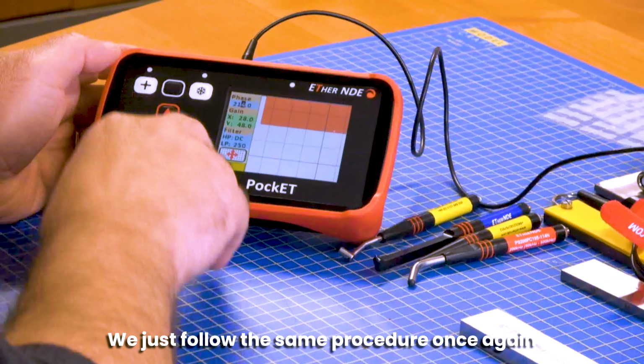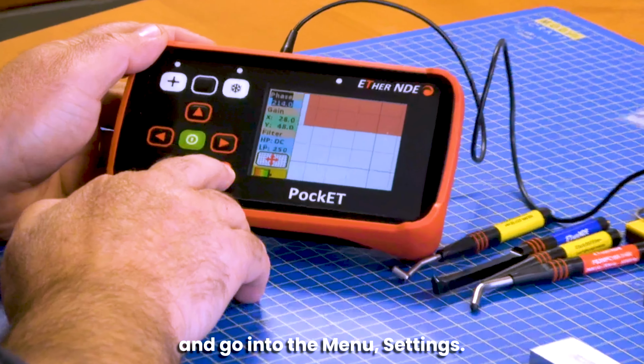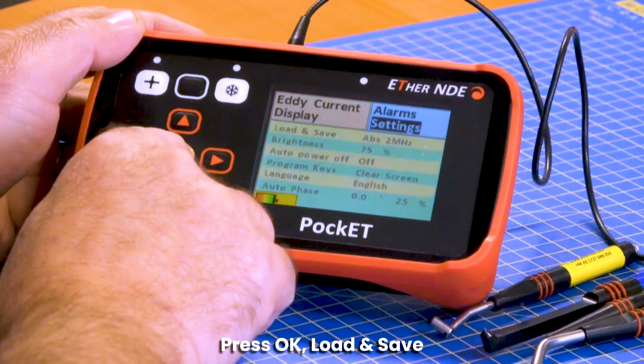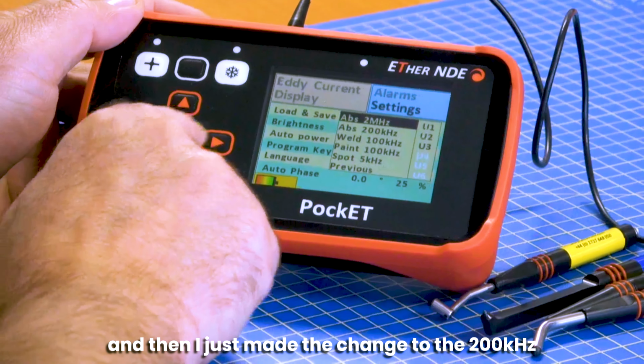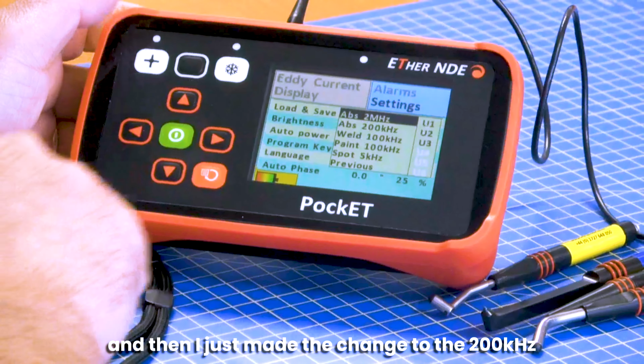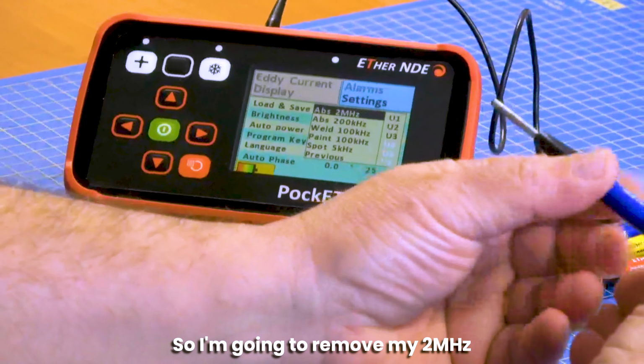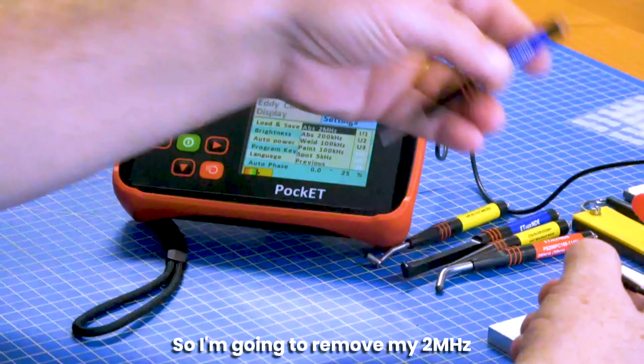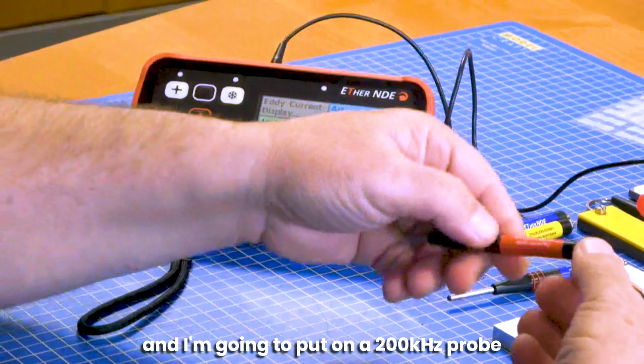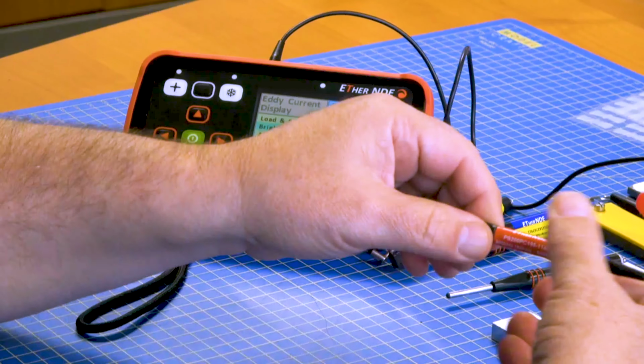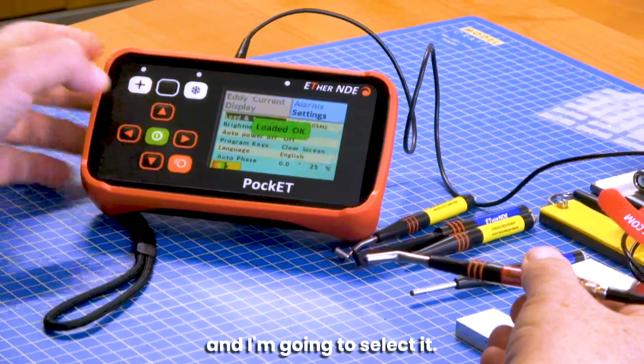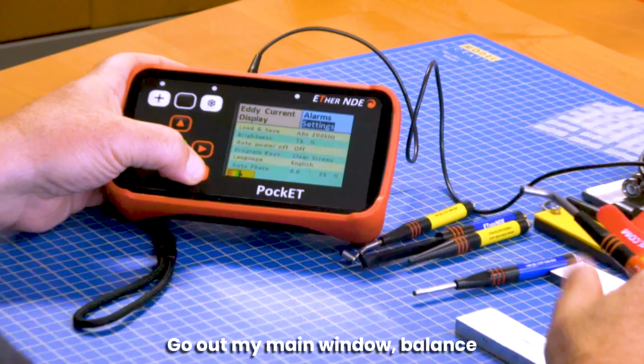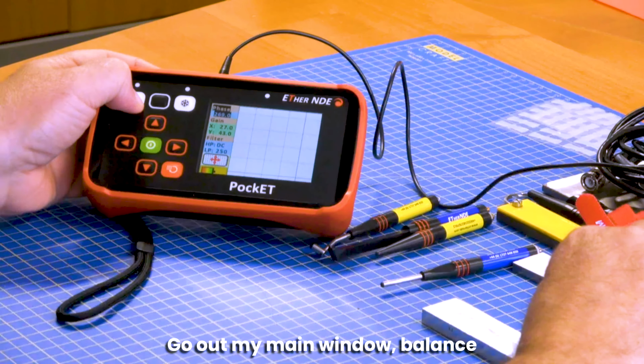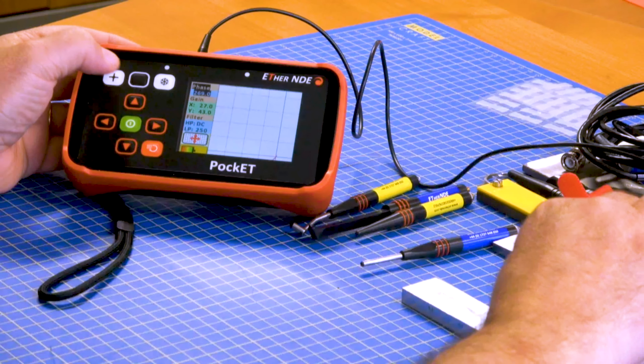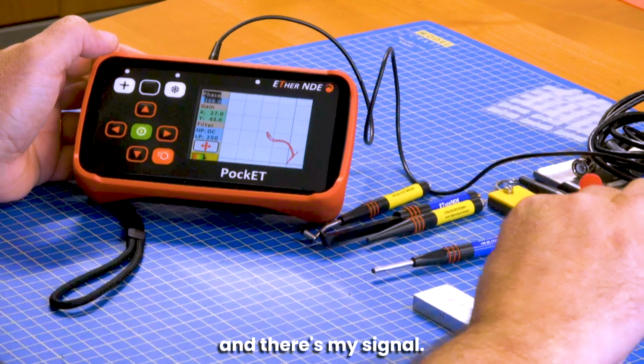The same can be done with the 200 kilohertz probe. We just follow the same procedure once again. We go into the menu, settings, press OK, load and save, and then I just make the change to the 200 kilohertz signal as I'm going to do right now. So I'm going to remove my 2 megahertz and I'm going to put on a 200 kilohertz probe. I'm going to select it, go out to my main window, balance, and there's my signal.